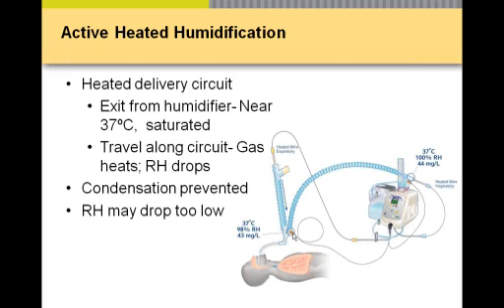As it warms the gas on the way to the patient, that's meant to prevent rain out. But your basic absolute humidity from that heater is still going to be related to the temperature, around 34 degrees Celsius. And so that's the water that you're delivering. So if you have that and you're still seeing rain out along this tube, then you know your gas has to be cooling to less than 34 degrees Celsius to actually see rain out along the tube.